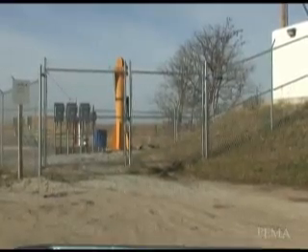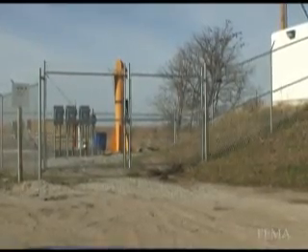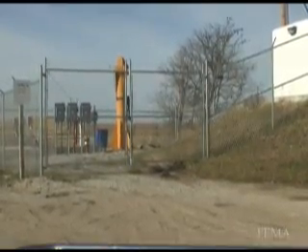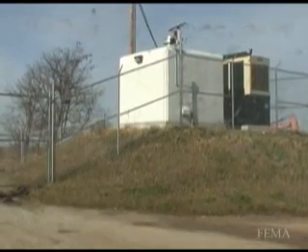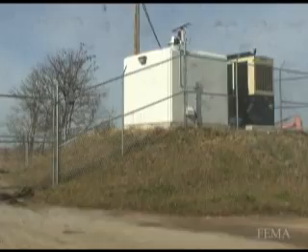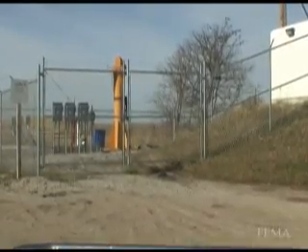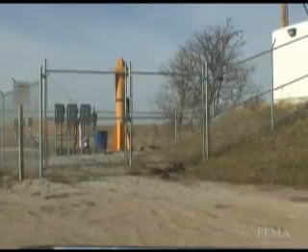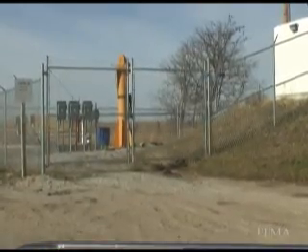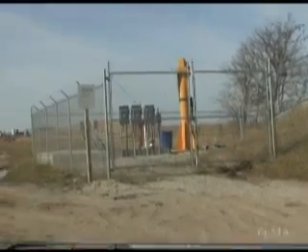We became immediately proactive during the flood to elevate everything we could to higher elevations, so we feel we're extremely well protected. We also changed the design criteria on our lift station. Before, the whole town of Peotone ran through two 10-horsepower pumps — a total of 20 horsepower pumping the sewage. Now I have three 100-horsepower pumps.